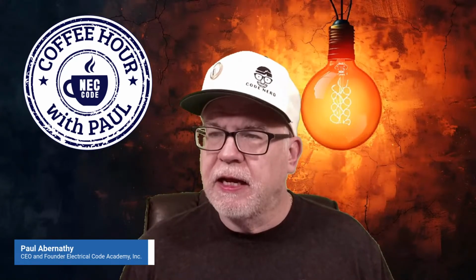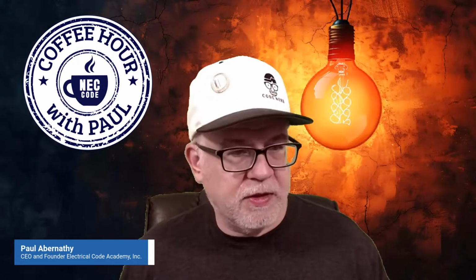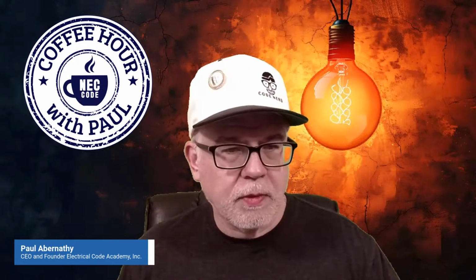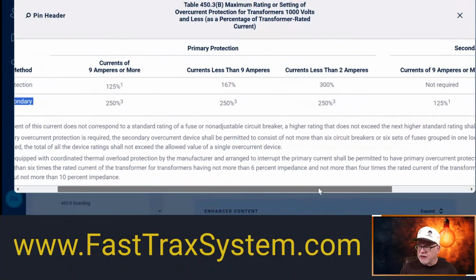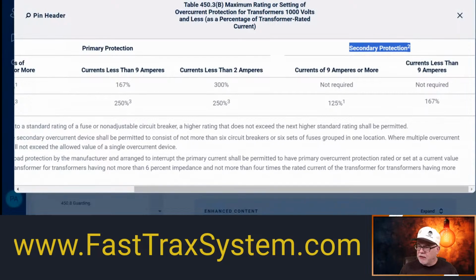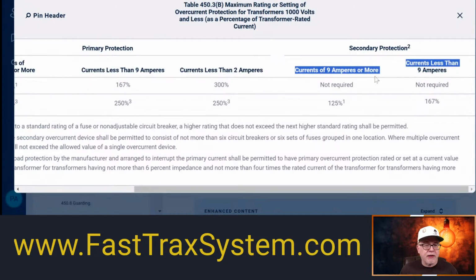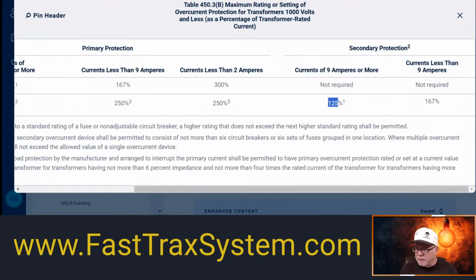All right, so at 208 amps, just go with me here. Let's go to the code real quick. Let me show you. At 208 amps, it says, here is a secondary protection, and it definitely is 9 amps or more. We're still at 450.3(B), by the way. It says 125%. So if I had 208 amps, 208.2, or just 208.18, use the pure amount if you want. Doesn't matter in the field. Use 208. But I'm going to use the exact amount we had, 208.18, just for fun. I'm going to go 208.18 times 1.25, and that is 260.225. You're now sizing the overcurrent protection for the secondary.